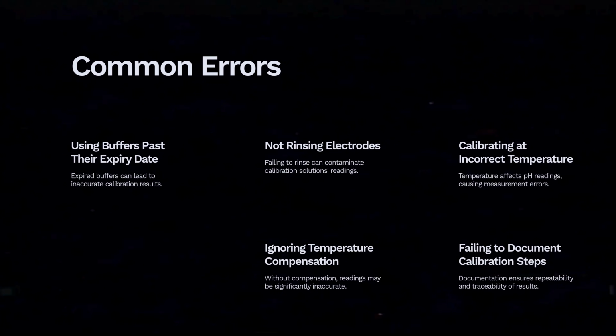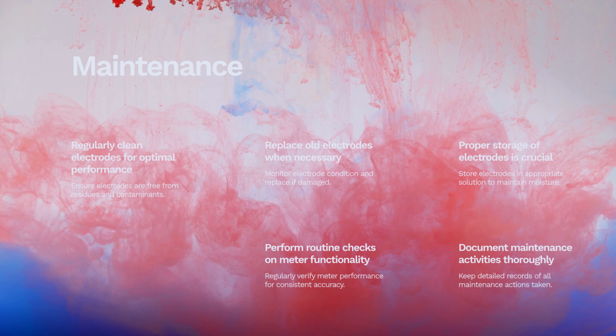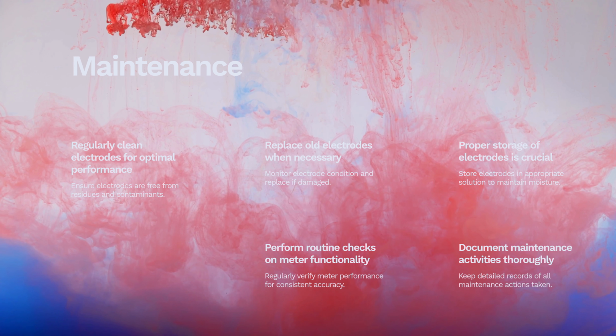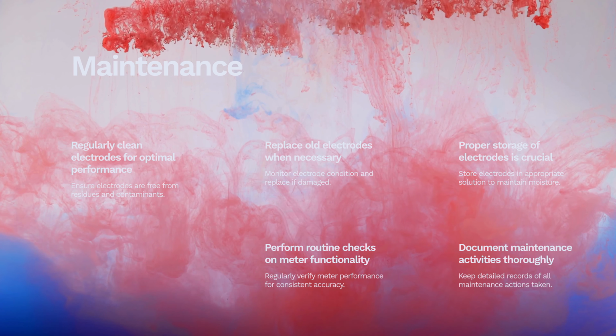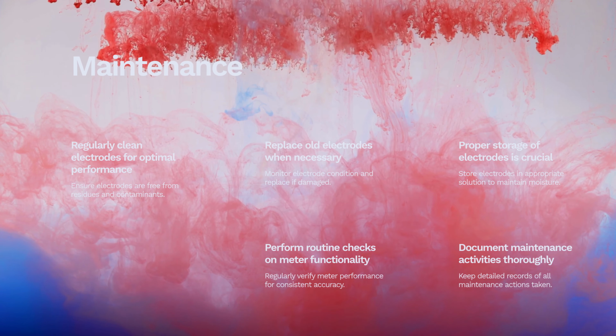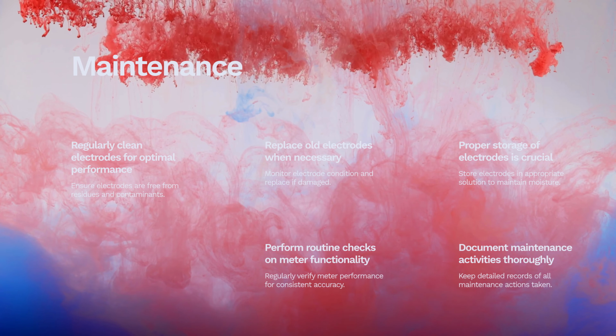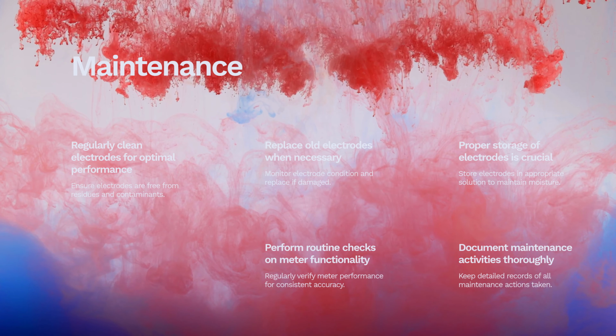Regular maintenance is vital for the continued health of your equipment. You should clean your electrodes frequently to remove any chemical residues, store them in the correct storage solutions to maintain membrane moisture, and proactively replace old or damaged electrodes. These simple steps ensure your meter always functions at its peak performance level.